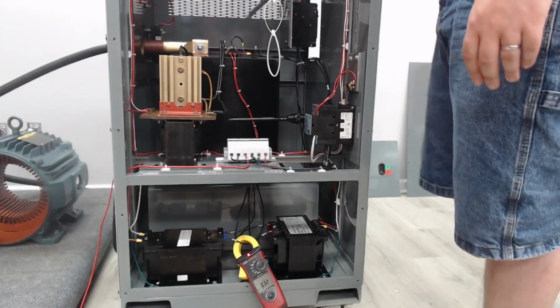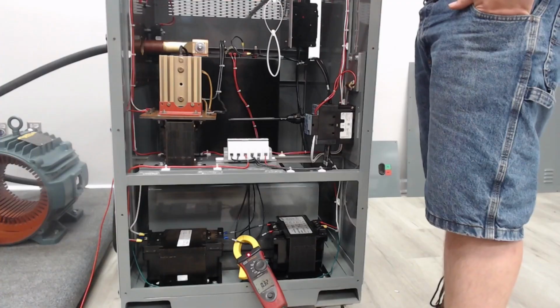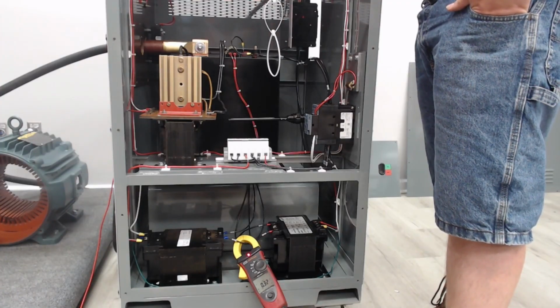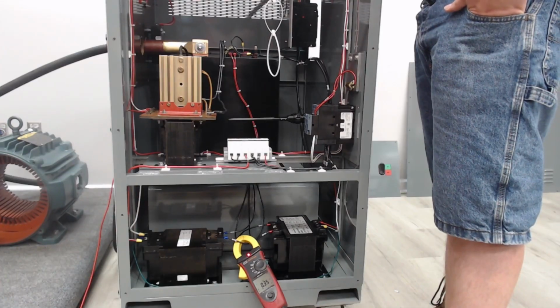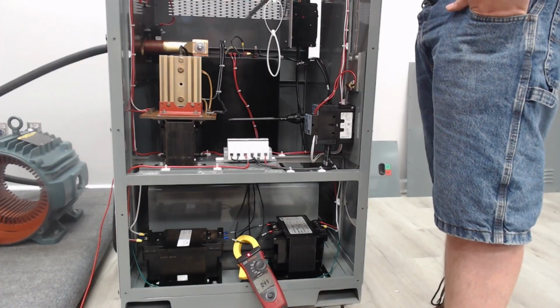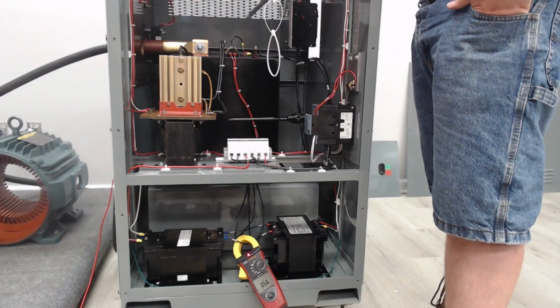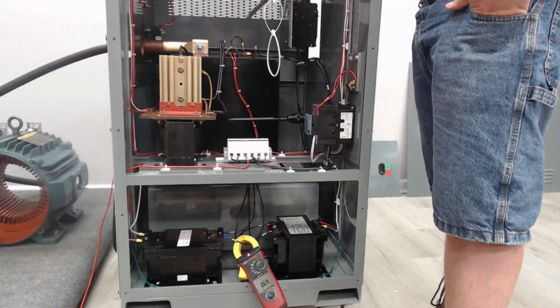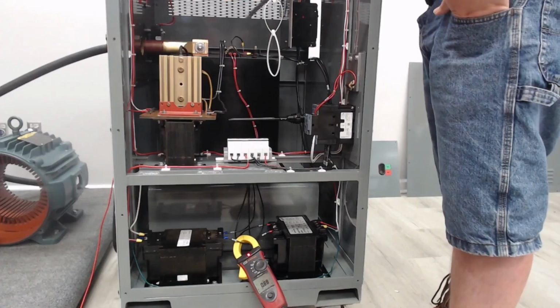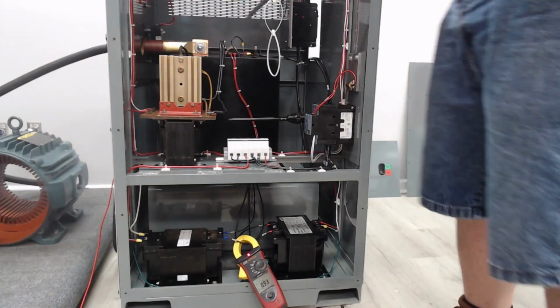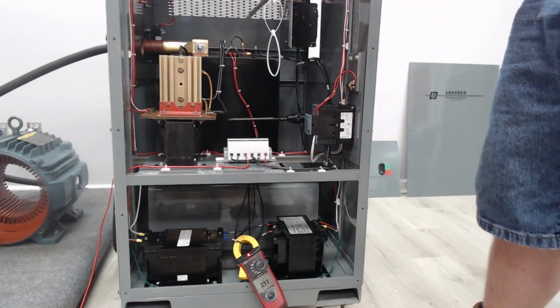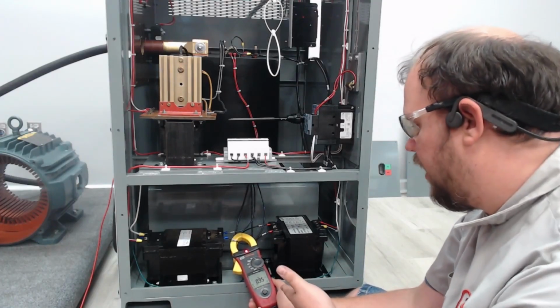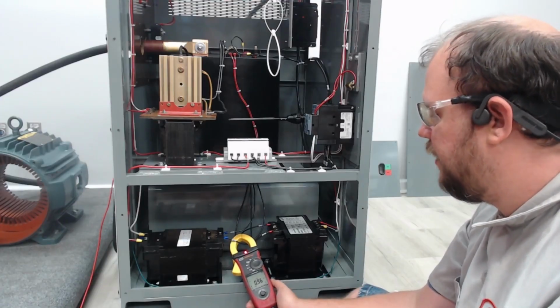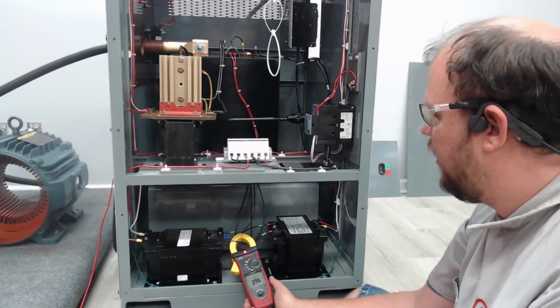All right, contactor is on, unit is humming. I am slowly ramping the unit up. All right, so I am currently at max what the armature will allow. That's not max of the unit. It may not be max for your unit, but I'm as far as it's going to allow with our current setup. So if we look now, it is at 0.93, 0.95, basically 1 amp. 1 amp is what I'm pulling, and it's going to stay that way. That's the max of what I should be getting with my current setup.